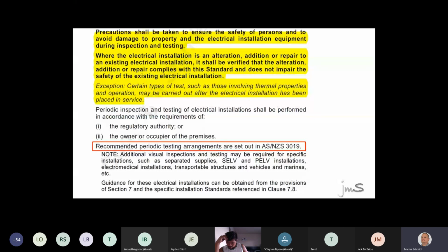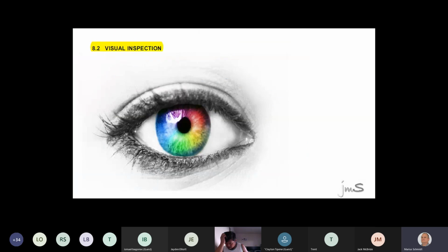But in 3019, it actually states, when you have got an installation, you don't just check the wiring, you also check if the fittings are correct. Have you installed the right current rating light switch? You can't put a 30 amp breaker on a 1 mil cable. Make sense? So you must use a bit of law knowledge as well. Some of you guys know that for a 1.5, you're going to use a 10 amp breaker. But where does it come from? The 3000 book. Now that's a regs exam. So it says here that you must make sure that all tests are correct and your fittings are all electrically safe. Good. Visual test. You guys will laugh.